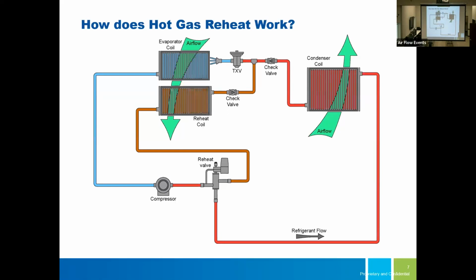Question regarding what kind of differential we're looking for with the reheat coil, and how is it technically sized? We have a discharge temperature coming off of the evaporator coil, and what is the optimum delta T that we're looking to increase for optimizing dehumidification? Is that a variable in the way this is designed, or is this a one size fits all solution?